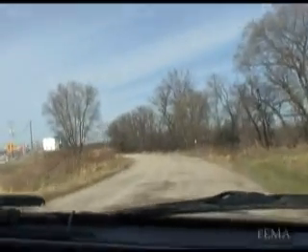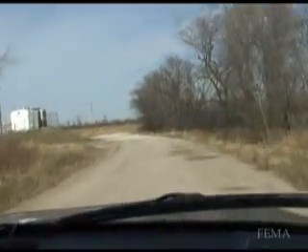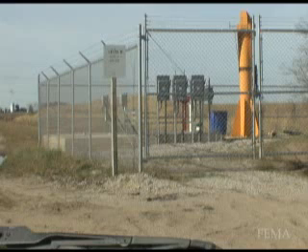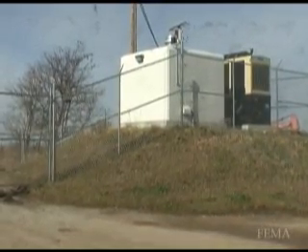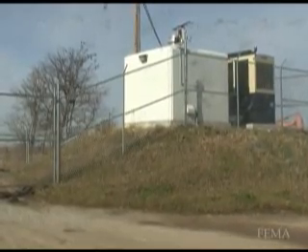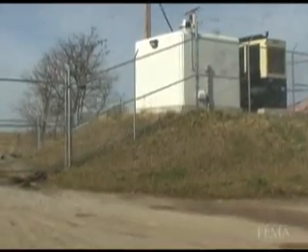One of the things we redesigned — you notice the mound of dirt that our generator and control panel sit on. The original design standard was at the height you see with the concrete pits, and they were installed before the flood. After the flood, we decided to raise it, and now the height of the building and our generator is a good two feet above the 2008 flood level.